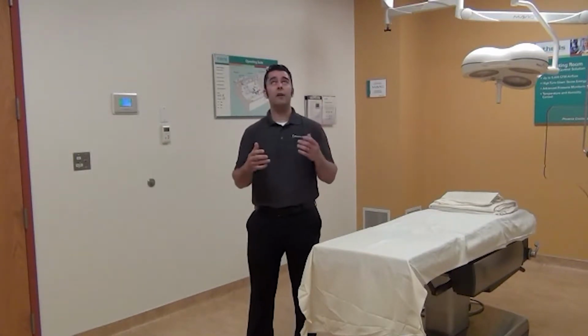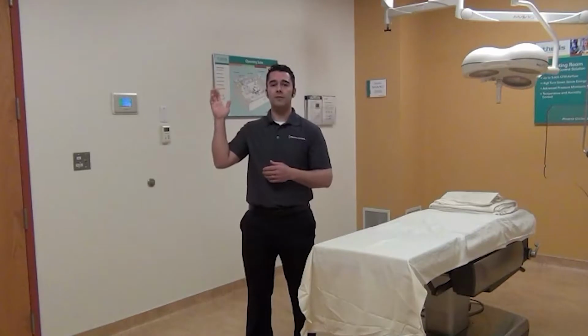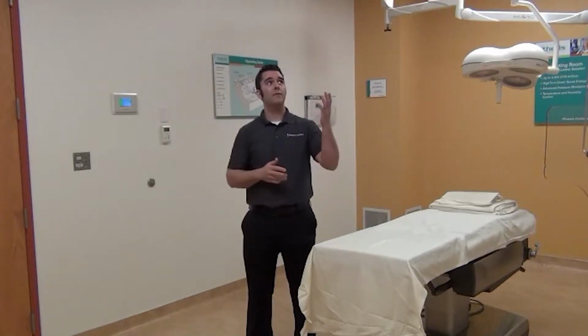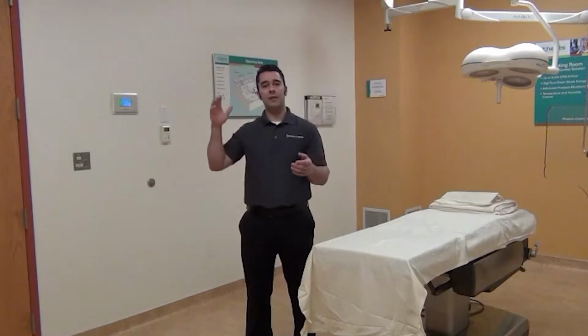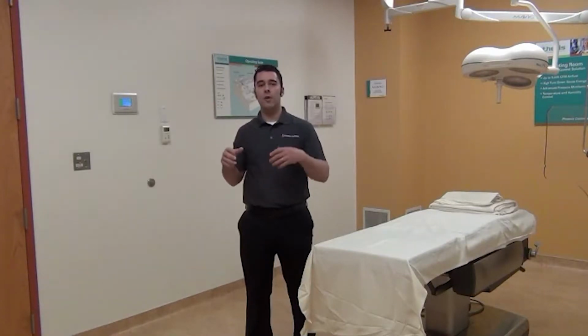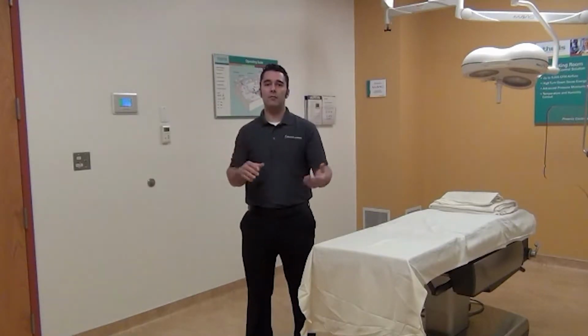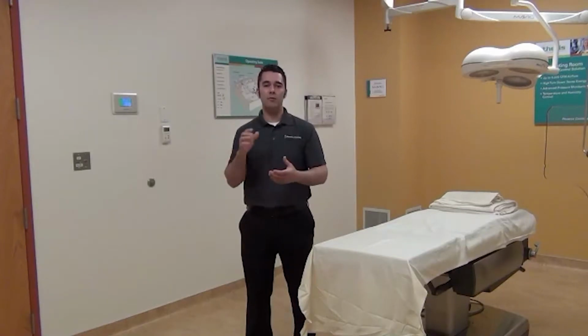So in this type of environment, again, we're using a Phoenix Controls tracking pair. We're using the Theris product line, which is our healthcare product line. And in here we have a supply Phoenix valve and an exhaust Phoenix valve. We also have some Nailor terminal boxes on the other side of the room. So we have some unique setups in here where we have bubble tight dampers that will actually isolate either the Phoenix Controls side of the room or the terminal box side of the room, so that we can demonstrate how the two different products work in this type of an environment.